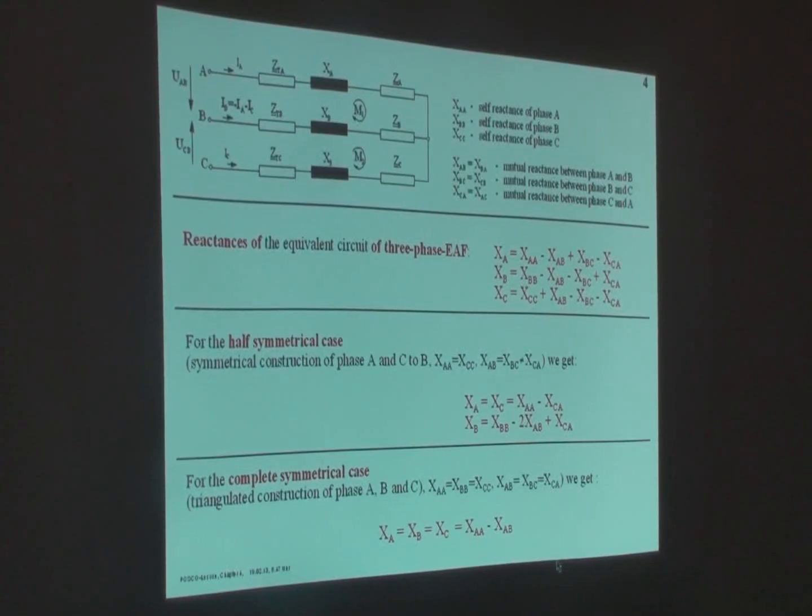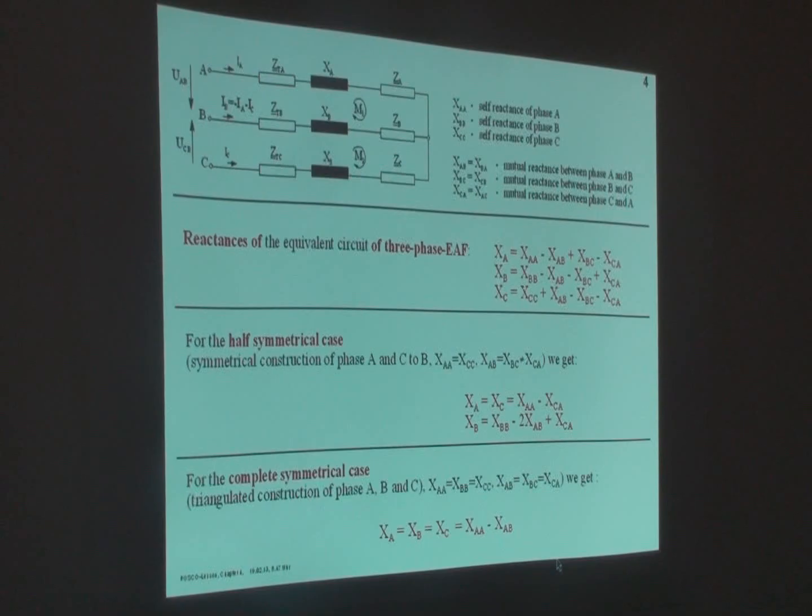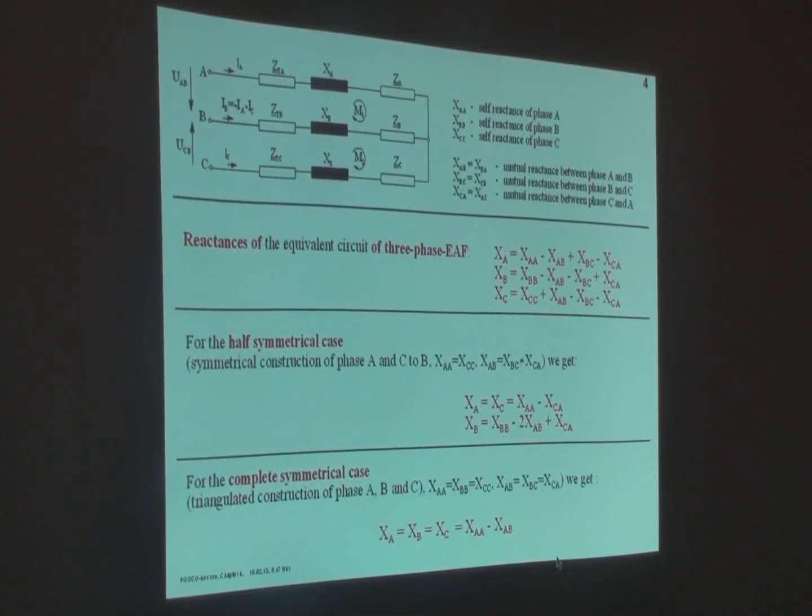That's the exact calculation. You will see the reactance in phase A and C is double that in phase B. That's not good, because the power is different in the phases. Therefore, you have to do something.